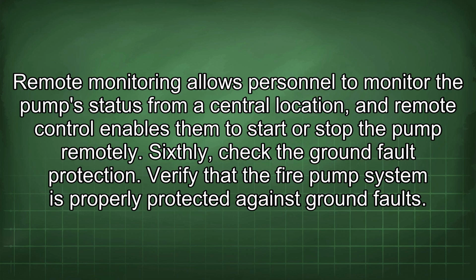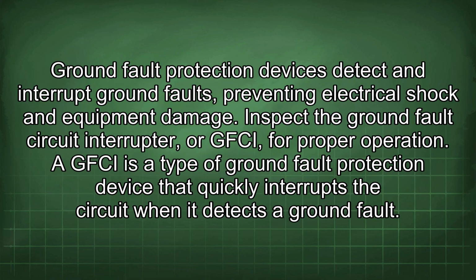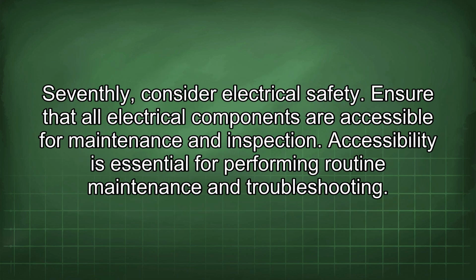Sixthly, check the ground fault protection. Verify that the fire pump system is properly protected against ground faults. Ground fault protection devices detect and interrupt ground faults, preventing electrical shock and equipment damage. Inspect the ground fault circuit interrupter, or GFCI, for proper operation. A GFCI is a type of ground fault protection device that quickly interrupts the circuit when it detects a ground fault. Seventhly, consider electrical safety.